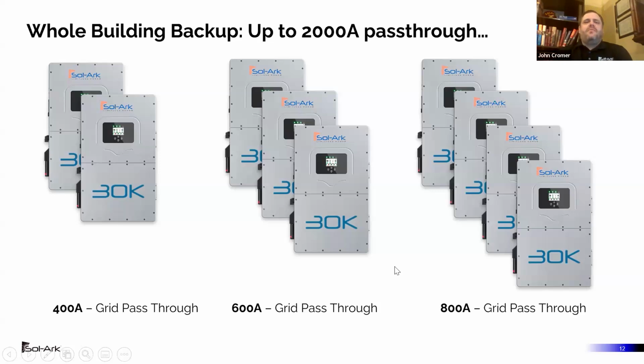So the first is that whether you're using our 30K for 208 volt or our 60K for 480 volt inverter line, we have a feature called a grid pass-through, and it's 200 amps per inverter. So for your minimum project size, if you want to back up the whole building, the minimum would be 2 inverters for 400 amps, 3 inverters for 600 amps, or 4 inverters for 800 amps. You have to be a little bit careful with that grid pass-through capability because the inverter can only back up a subset of that 200 amp service. So you have to know your loads.